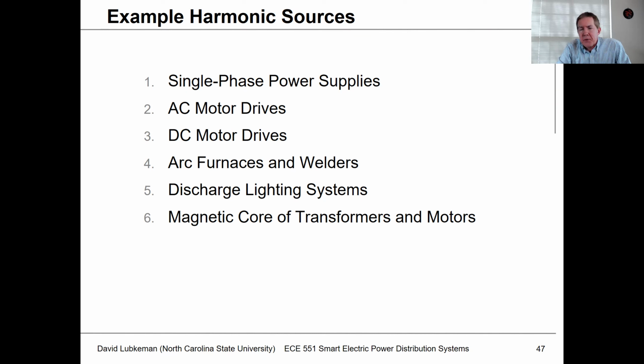Another thing that would create harmonics is also transformers, because transformers have magnetic cores that are nonlinear. And if you have single phase transformers, these can actually generate third harmonics. So anything that has a magnetic core is going to saturate, and is also going to have harmonics associated with it.